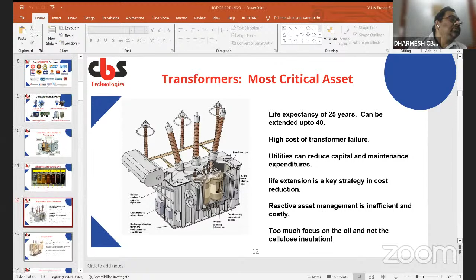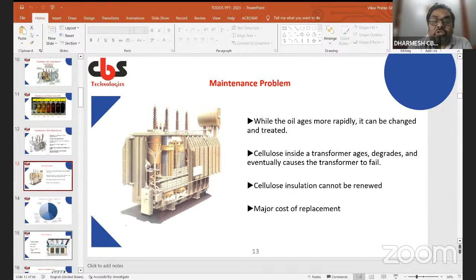Here the maintenance problems are narrated. While the oil ages more rapidly, it can be changed and treated. Cellulose inside the transformer ages, degrades, and eventually causes the transformer to fail. Cellulose insulation cannot be renewed, and the replacement is a major cost.